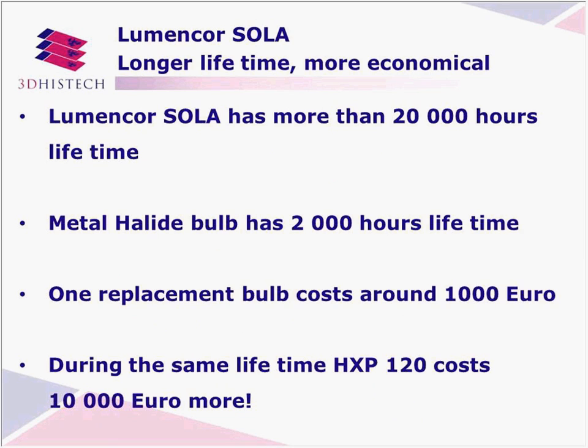Of course, the SOLA has more than 20,000 hours of lifetime. Since it's a solid-state, basically LED-based light source, it's not the LEDs that go wrong. It's more the ventilation, electronics, or something. So if after 20,000 hours there is something wrong with the lamp, it can be sent back to service. On the other side, the metal halide bulb of the HXP 120 has a 2,000 hour lifetime, and the replacement bulb costs the customer around €1,000. Over 20,000 hours, the HXP box has to be replaced, which costs €10,000 more.